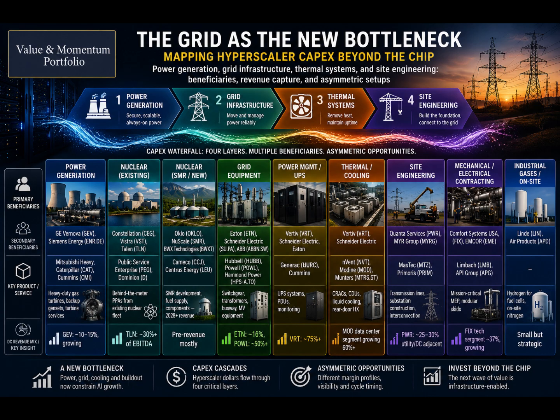Next, thermal management and cooling. Data center racks packed with graphic processing units generate a substantial amount of heat. For instance, the NVIDIA GB200 NVL72 setup operates at roughly 120 kilowatts per rack. Looking ahead, future Rubin platforms are targeting 250 kilowatts plus per rack.